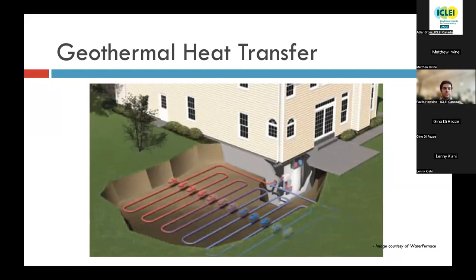But in essence, what the heat pump earth loop is doing is providing a very large amount of low-grade heat that is brought back to the heat pump and put in contact with the refrigeration cycle, where using the compressor, it is compressed into a usable amount of high-grade heat. And then that heat is distributed into the network, or into the ductwork, in a forced air system. But it is not just a passive heat exchange process. And because we have this energy source in the wintertime underground, and we're not just burning a fuel, we're able to achieve much higher levels of efficiency. Geothermal systems are typically described as, or their efficiency is described in terms of a COP, which stands for coefficient of performance. Next slide, please.